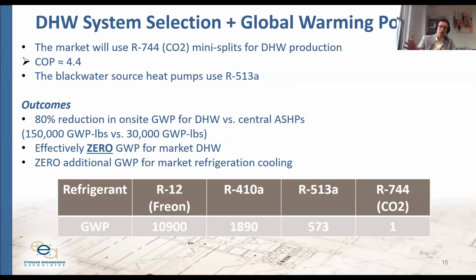The other thing, and we'll look at the spatial design of the market on the next slide so this gets driven home better once you can see the imagery, is that through artful design we're able to do mini split domestic hot water systems for the market. These aren't great at large scale buildings, they have very short limitations on the refrigerant piping they can accommodate, but we found a way to put CO2 mini splits in for the actual domestic hot water production of the market itself.